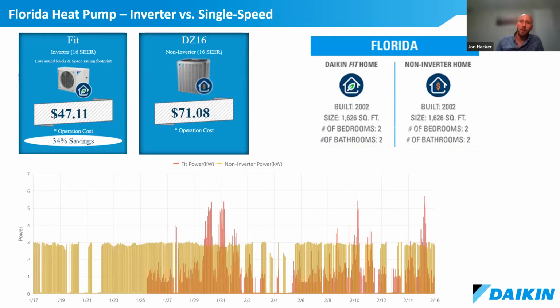The yellowish line is for the non-inverter system, 16 SEER, so it's the same efficiency rating. The darker, more orange bars are for the inverter product. There are a couple of observations here, and they're going to be pretty consistent as we go through these. Just to drive the point home, for the non-inverter system, the power consumption is roughly fixed. It's either off or consuming about 3 kilowatts of energy. For the inverter product, you see a lot more variability. For this particular application, sometimes it's operating at 1 kW, other times at 2 or even all the way up to 5.